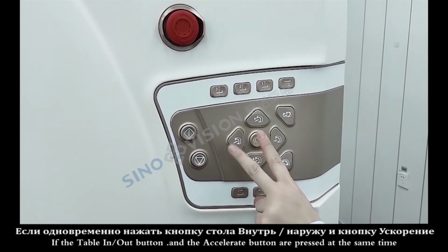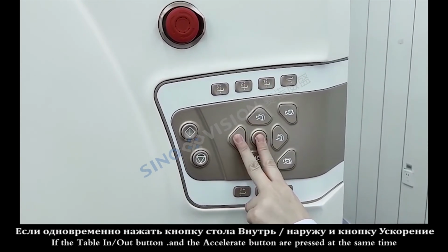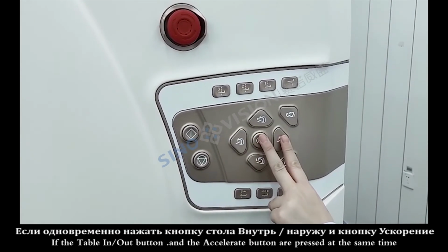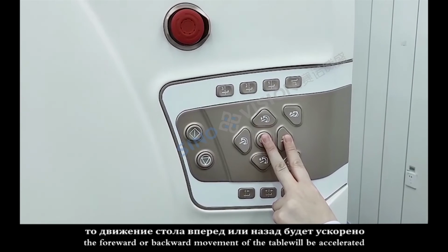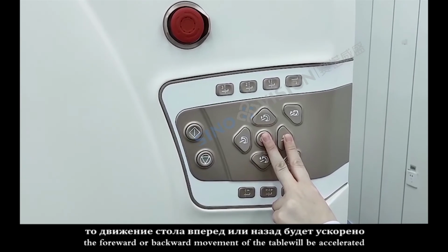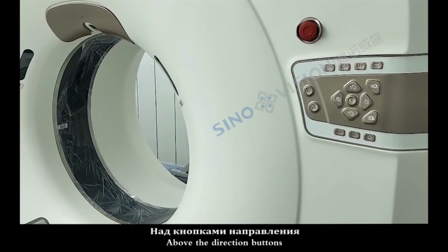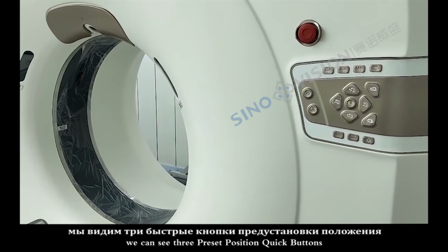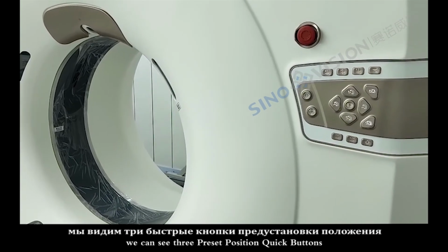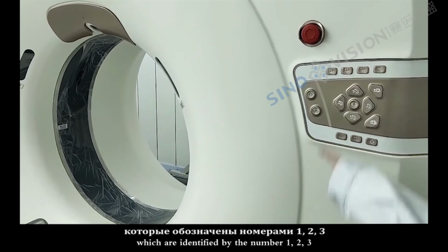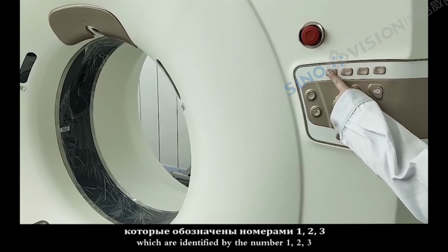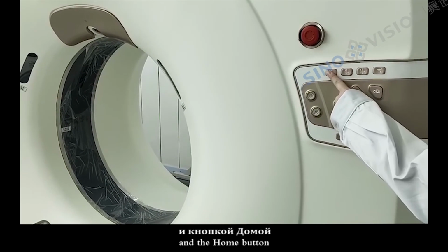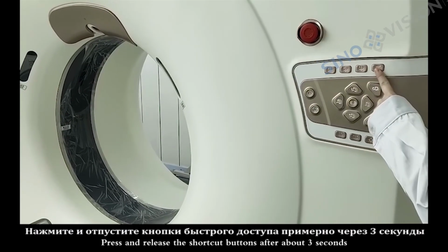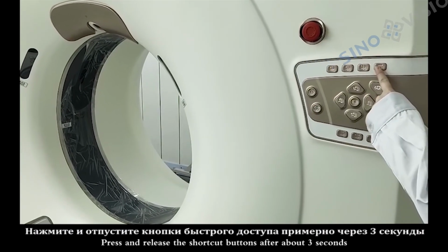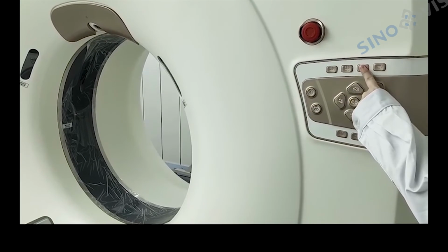If the table in, out button, and the accelerate button are pressed at the same time, the forward or backward movement of the table will be accelerated. Above the direction buttons, we can see 3 preset position quick buttons, which are identified by the number 1, 2, 3, and the home button. Press and release the shortcut buttons after about 3 seconds.